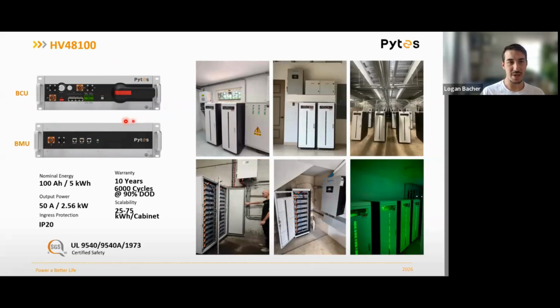Most of the action is going to be happening with your control unit, or your BCU. You can see, we'll see better later, but that is usually at the top of the cabinet or at one end of the battery group. That's the user interface - this is how you're turning the battery group on and off. This is the thing that's controlling all the batteries, this is the thing that's talking to the inverter. There's no cells in this piece - it doesn't hold or release energy. It's just the master controller for the group where all your cables connect to.